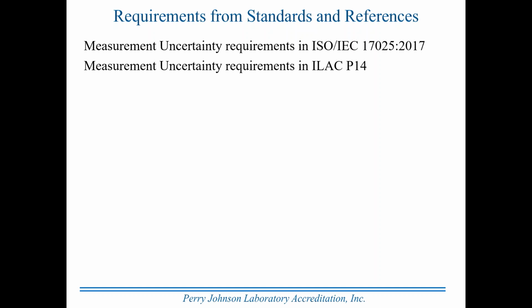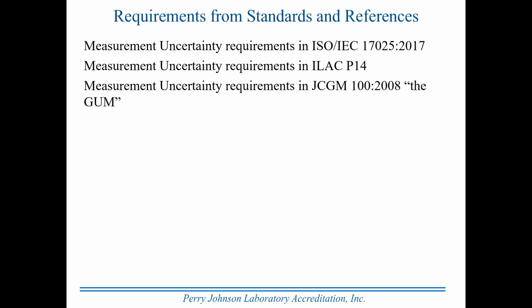Measurement uncertainty requirements in ILAC P14, and ILAC is the International Laboratory Accreditation Cooperation. They publish a series of documents. There are some guidance documents, which are the G series. There are some policy documents, or procedural documents, which are the P series. P series documents will be imposed on laboratories through the accrediting body. ILAC publishes a procedural document. The accrediting bodies are obligated to ensure that the laboratories they accredit operate in compliance with the ILAC procedural document. So we'll be looking at some of the issues and some of the requirements found in P14 related to measurement uncertainty. Measurement uncertainty requirements found in the GUM, we're going to look at some of those.